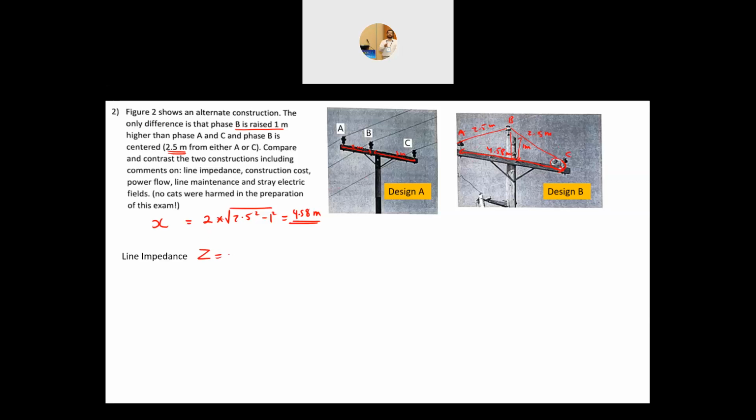Now, let's talk about the line impedance. As you know, Z is equal to R plus j omega L. R doesn't change. If I change the configuration of the line, R doesn't change. What does change is your L. Now for design A, we did the calculations before.